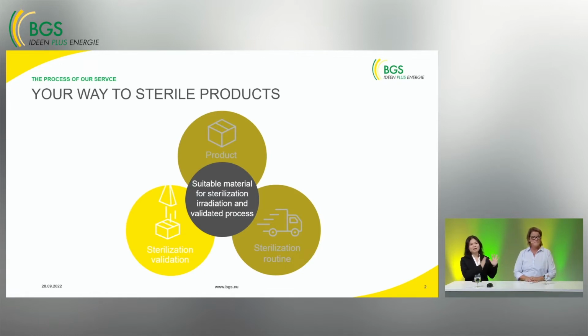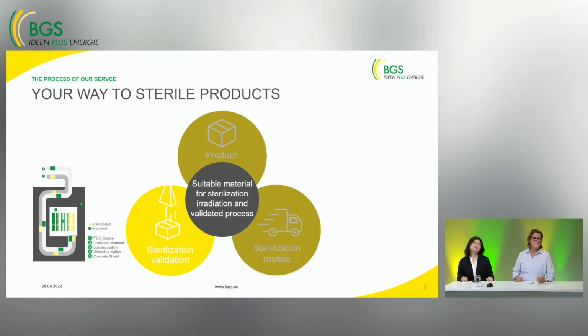After all of those have been clarified, we can go ahead with the sterilization validation, also called performance qualification or dose mapping. Both E-beam and gamma are regulated under DIN EN ISO 11137, and relevant for the validation are Part 1, requirements for development, validation, and routine control of a sterilization process for medical devices, and Part 3, guidance on dosimetric aspects of development, validation, and routine control.